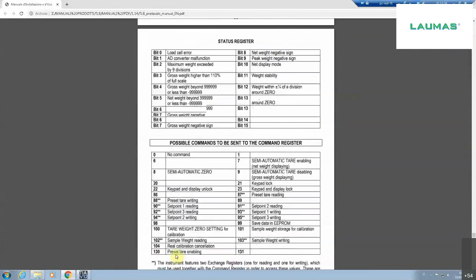So, we can go back here and define a command register tag. It is a 2-byte field, so we can define word as data type. But we have to change the address, switching to Q, corresponding to the PLC output data area, and we have to set the starting address to 256.